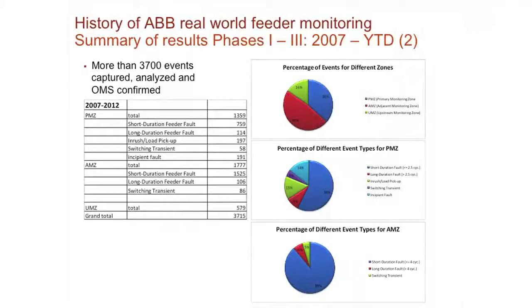And then also we used the time to actually select different feeder topologies. Even though they wanted to know about underground cables, we also put in some overhead feeders that had primarily overhead sections. We had some feeders we chose that had a mix of underground and overhead. And in some cases we had an entire bank. So in this case, 4 feeders, and we see what kind of information we can get from having all 4 feeders monitored on one bank. So this is some of the results.